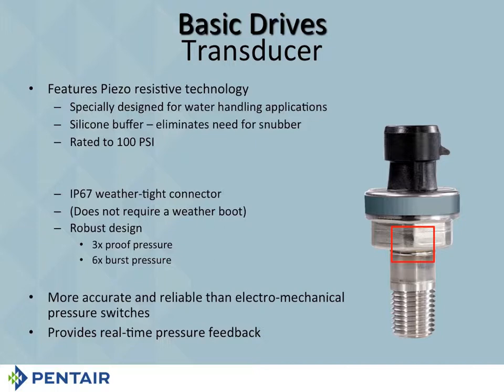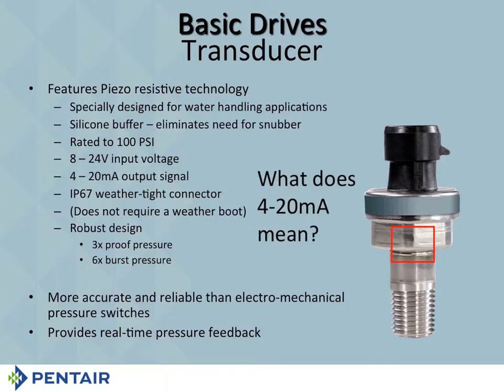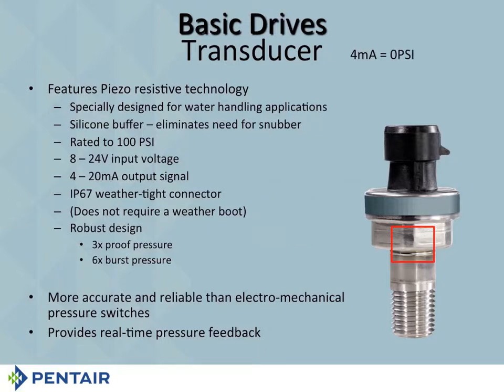All right. It is 8 to 24 volt input with 4 to 20 milliamp output. What that simply means is this: 4 milliamps is going to be zero pressure. 20 milliamps is going to be your max pressure, which, if you're using the transducer we give you, is 100 pounds. If you divide, there's actually 17, because these are inclusive numbers. So if you divide that 100 pounds by the 17, you're going to find about 6 pounds per milliamp.